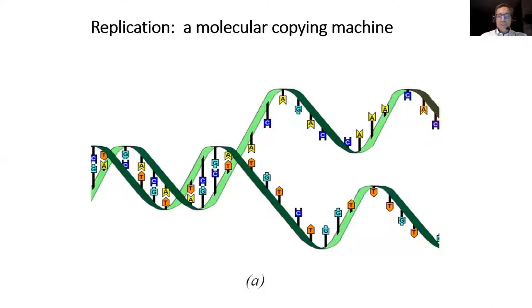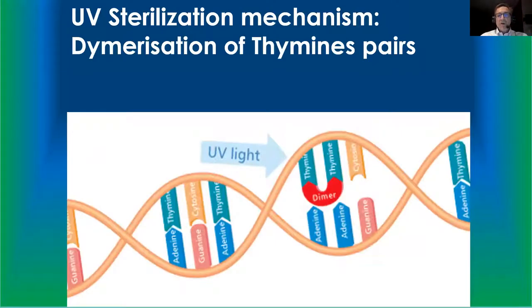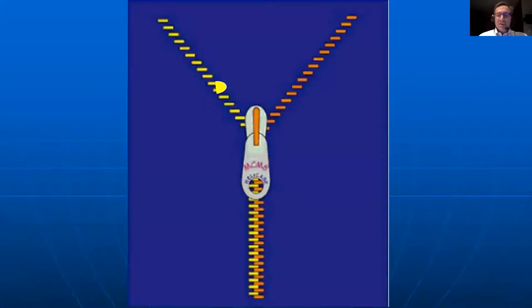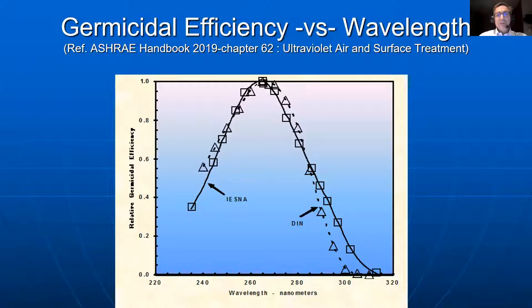What we do when we bombard this molecule with UV, we are actually altering this molecule at several points. It's called dimerization of thymine pairs. When you have two adjacent Ts, we bind them together with the UV light at 254 nanometers, the UVC. As a result, when this molecule tries to reproduce again, it's jammed. I like this analogy: it's like a zipper when you have two adjacent pins that are melted together, your zipper will not work. So it's really mechanical. And if you make enough damage on that zipper, which is the molecule that tries to replicate, it will become sterile. It will not be able to infect a host. And as a result, you're getting the disinfection process.